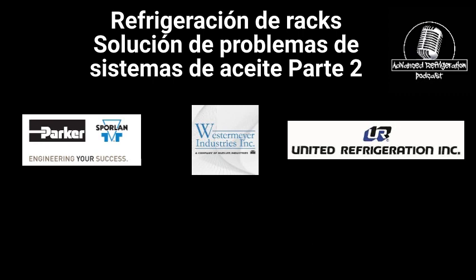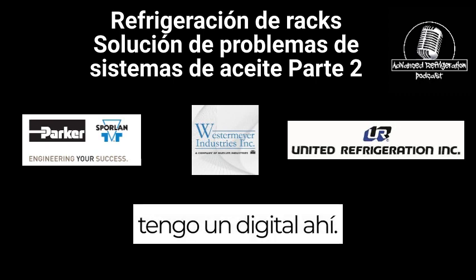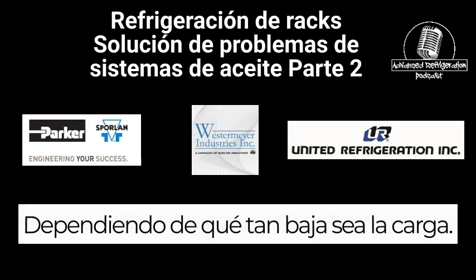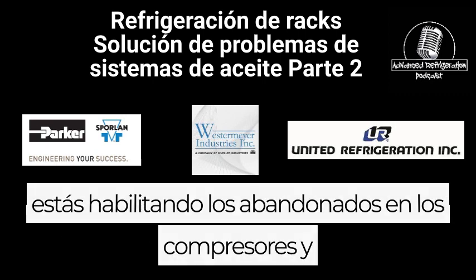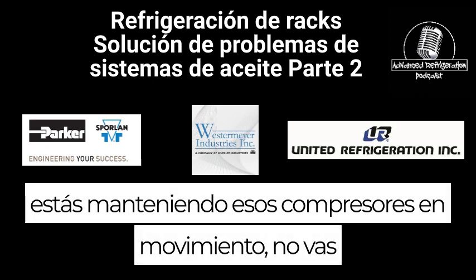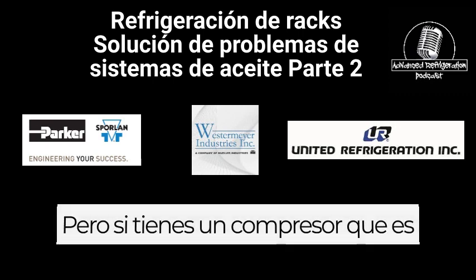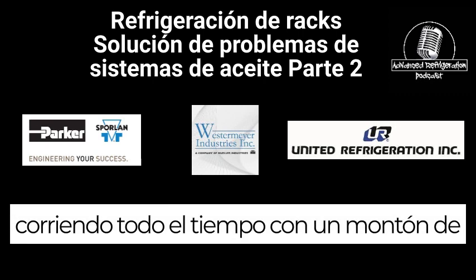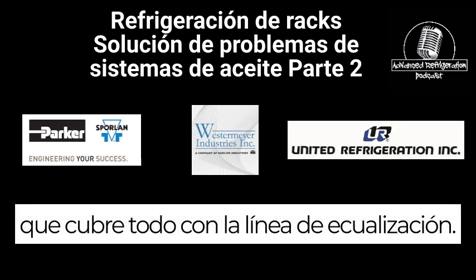It just depends. Copeland, if it's got a digital on there, you probably need to have it depending on how low the load is. If you've got a high load rack and you're enabling the unloaders on the compressors and keeping those compressors moving, then you're not going to have an issue in most circumstances. But if you have a compressor that is running all the time with a bunch of unloaders, you're probably going to need the equalization. I think that covers everything with the equalization line.